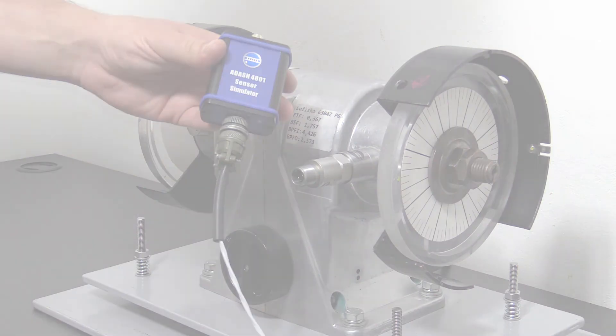Remember to set 100 mV per G sensitivity on this channel. Do you see values as per sensor simulator table? If not, you should check the cable and its connectors, because it is broken somewhere. If yes, then the sensor related to this channel is broken.